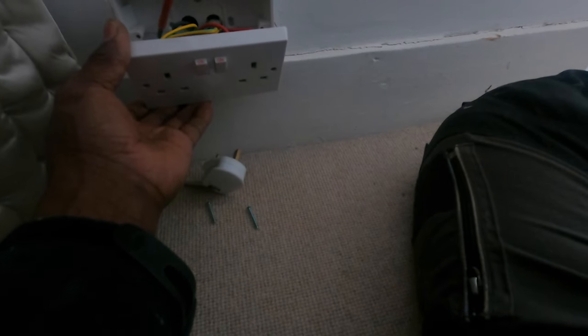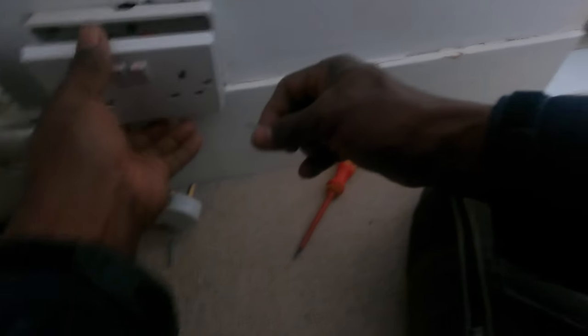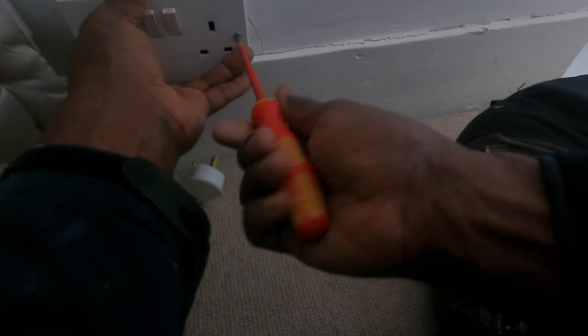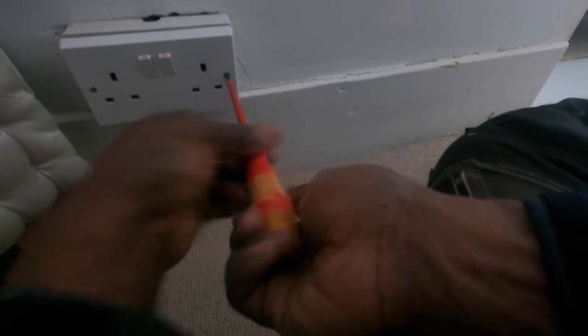The fixings are pretty tight. But this sparky — you don't know what they've done. Because when you see things like four cables in an MCB, that doesn't give you confidence in the standard of the job, to be honest. It's got to be MK, because that's the make of your fuse board. But like I said, they're discontinued so it's quite hard to get them, though sellers still have them. And it was at this point that I actually found the fault — that's all tight, so that should be okay.